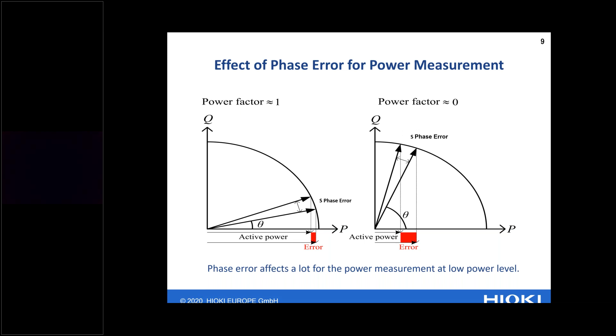So HIOKI is not only producing power analyzers, but also the current sensors. And having both of the development in-house gives us an understanding about the characteristics of each current sensor. And that means we were developing in the past years current sensors and this function in the power analyzers to do a phase shift correction. Because of the frequency spectrum or bandwidth, the higher we are in the bandwidth, the more problems we will have because of capacitance and inductance, and that will lead to a deviation of the phase angle, and that means you will have a phase shift.